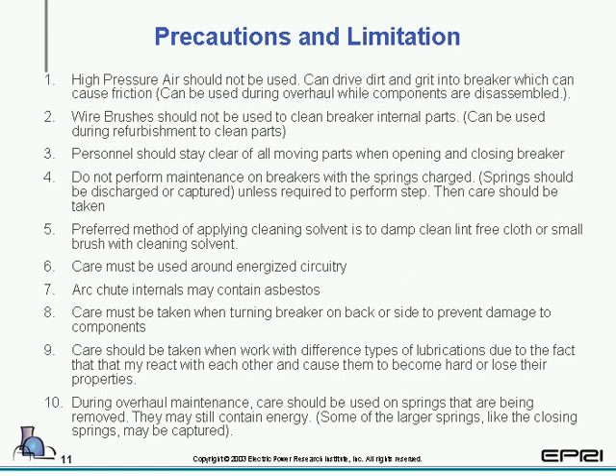Cautions and limitations. First one, high pressure air should not be used. That's on PMs. On overhauls, you may want to use high pressure air to clean out, especially where your pins ride or the parts ride on certain pins. Item 2, wire brushes should not be used. Again, that's on PMs. On overhauls, they're very effective for cleaning, especially silver parts. Personnel should stay clear of moving parts. Item 4, care should be used when working springs with the springs in a charged state.